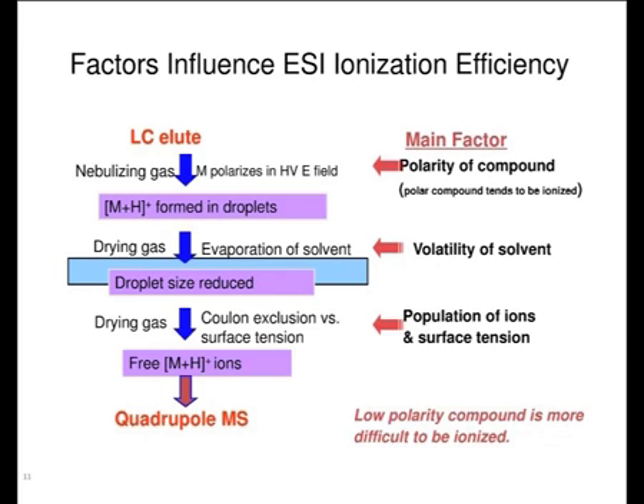Then the drying gas is used for the evaporation of the solvent. Because of that, the droplet size will reduce, and there is a competition between the Coulombic force of repulsion and surface tension. Then there is formation of free ions, and they enter the mass spectrometer.